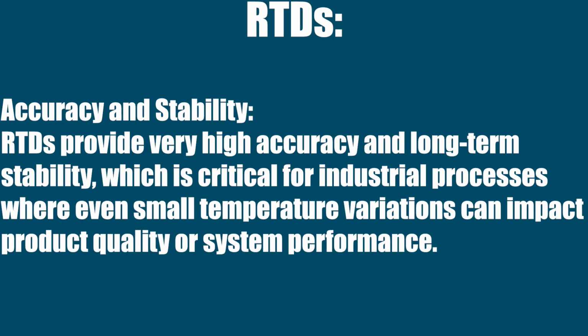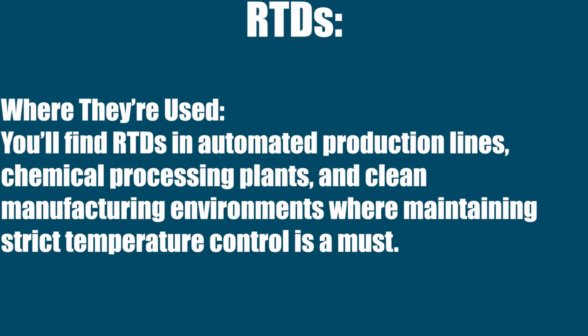RTDs are also highly favored because of their accuracy and stability. They provide very high accuracy and long-term stability, which is critical for industrial processes where even small temperature variations can impact product quality or system performance. You'll find RTDs in automated production lines, chemical processing plants, and clean manufacturing environments where maintaining strict temperature control is a must. Now let's talk thermocouples.